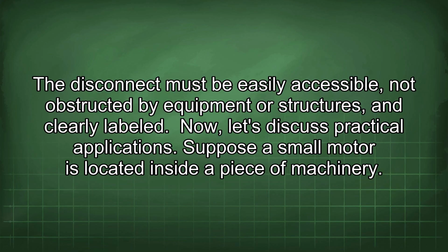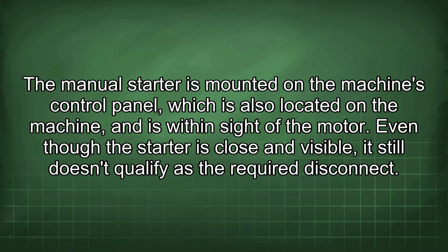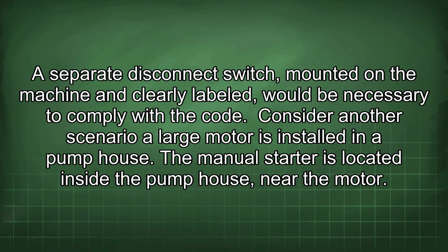Now let's discuss practical applications. Suppose a small motor is located inside a piece of machinery. The manual starter is mounted in the machine's control panel, which is also located on the machine, and is within sight of the motor. Even though the starter is close and visible, it still doesn't qualify as the required disconnect. A separate disconnect switch, mounted on the machine and clearly labeled, would be necessary to comply with the code.